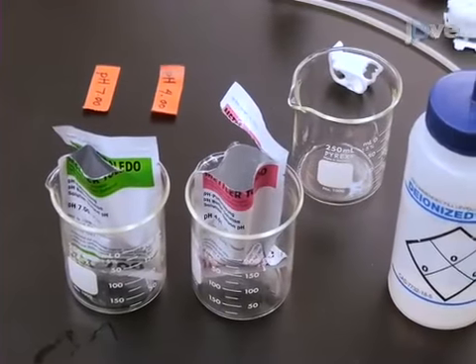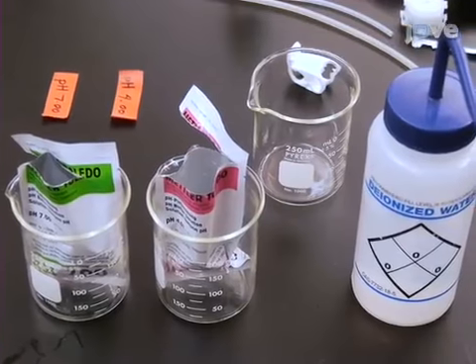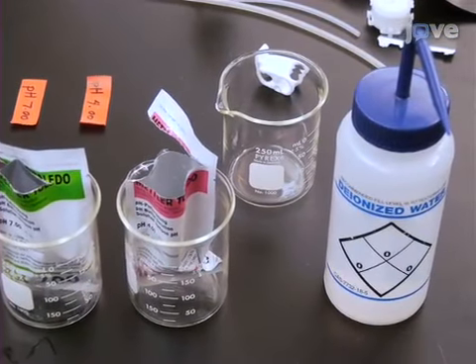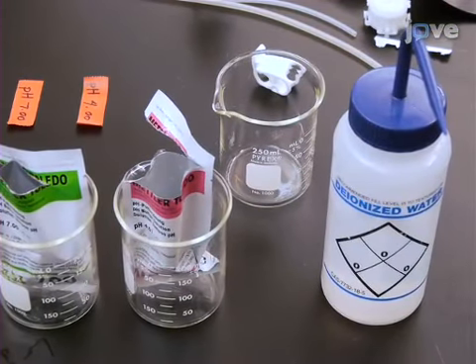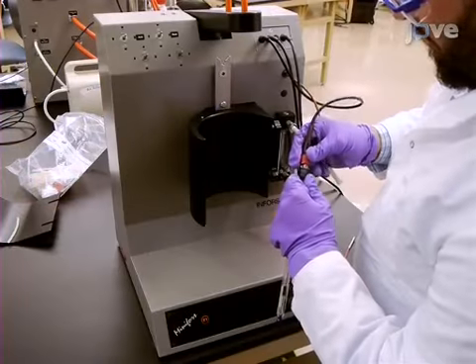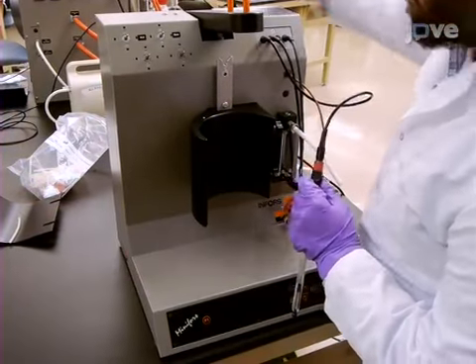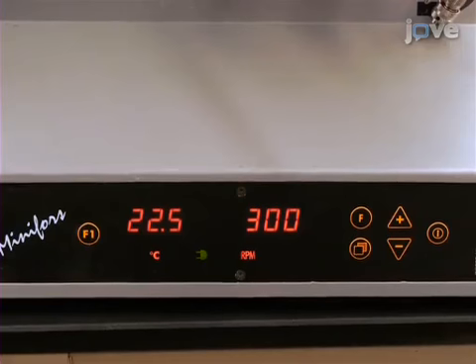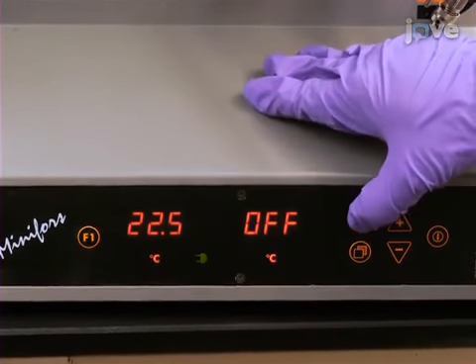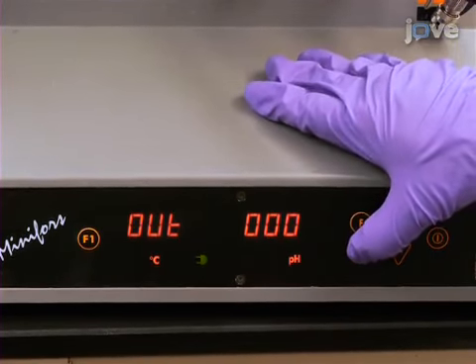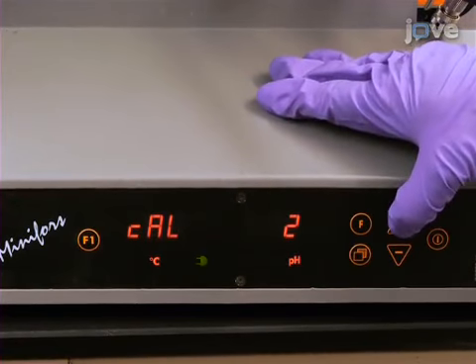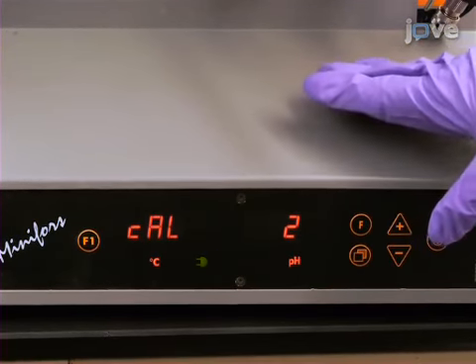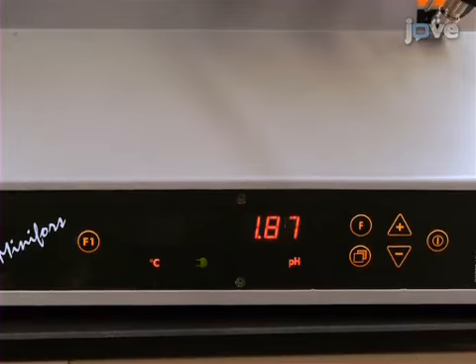To calibrate the pH probe, gather 2 reference buffers in small beakers, a wash bottle, and a wash beaker. Hook the pH probe up to the fermenter and turn it on. Scroll to the pH parameter and then, using the menu button, scroll to the Cal option and press Enter. Select 2 for 2-point calibration.